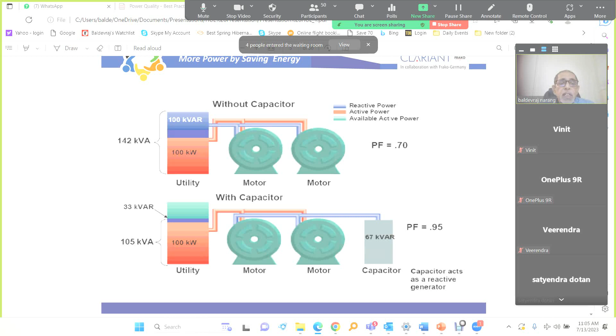So this is an example which gives more details about the reactive power, whether we import it from the grid or we have our own installation. Suppose we have a load with original power factor of 0.7, 100 kilowatt load. So at 100 kilowatt, the multiplying factor for reactive power is 1 only. So we need 100 kVAr of reactive power as well. And if we don't have anything, local capacitors or any other unit, active or passive, we will need to import 100 kVAr of reactive power also from the grid. And we'll need to take a sanction of 142 kVA for a load of 100 kilowatt.